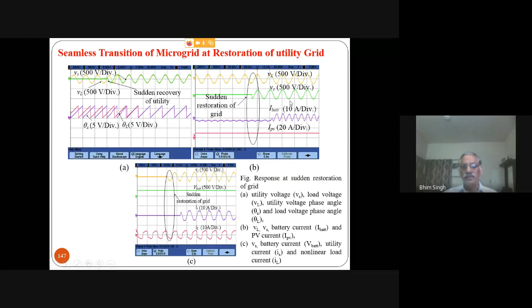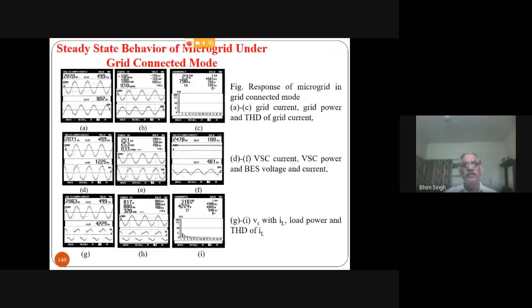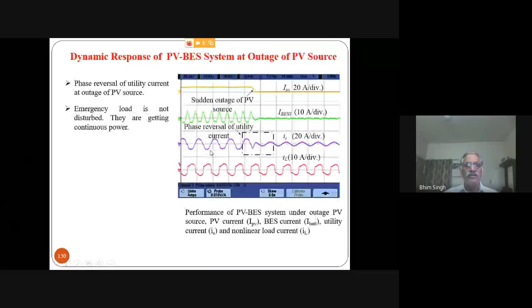And you can see how, after the grid appears, the angle floats towards the angle of the load voltage. The inverter puts its angle closer to the grid angle, and once the angle is close, and the voltage is already made equal to the grid voltage, all three conditions are satisfied and we close the switch. Closing the switch means grid current starts appearing here. You can clearly see the grid current start appearing here. So that is the synchronization. Islanding is very easy: you open the solid state switch and it goes very well. So we are able to do this synchronization, and we are able to get the THD quite low even when it runs in islanding mode.